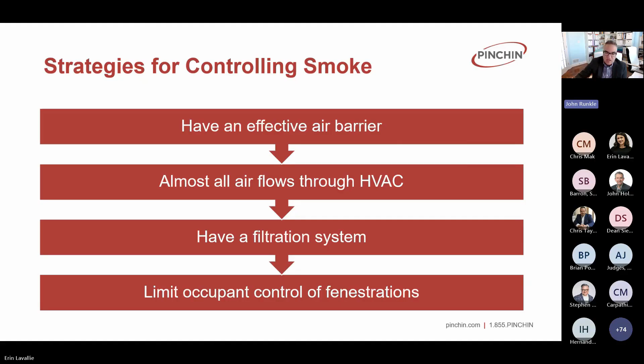So some strategies for controlling smoke, and you did hear Steve touch upon some of these as well. Having an effective air barrier, putting the airflow or almost all the airflow through HVAC systems is incredibly important. If you have a leaky enclosure, windows, roofs, or whatever, that's all examples of air coming into the building that's not being treated by the HVAC, and you really don't have a chance at that. If it goes outside of the filtration or cleaning systems, you've given up your ability to control that. And you want to limit the ability of occupants to alter the performance of the building, such as operable windows, which could wreak havoc if you're trying to clean air.